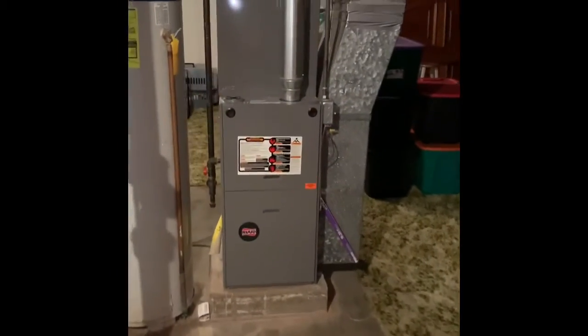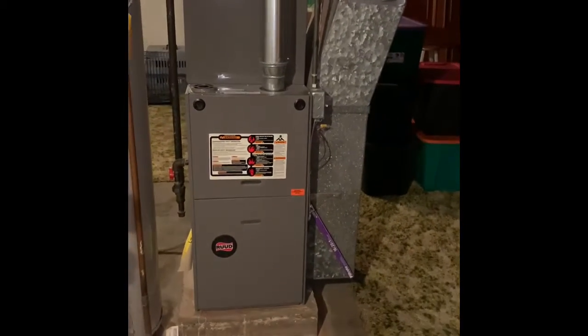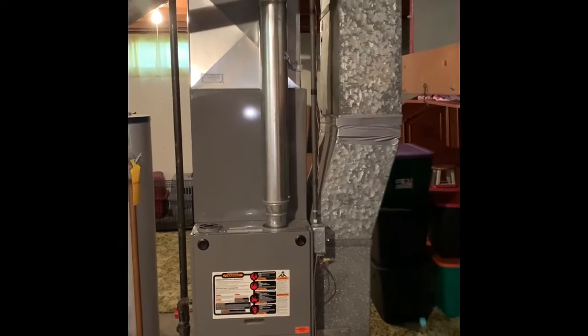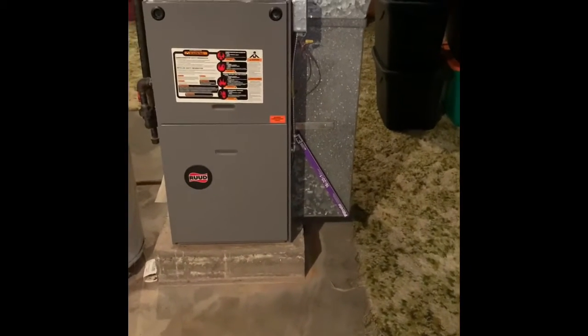Here's our inside portion looking at the AC system only. The system is from 2012 but they've already had two coils replaced, so I'm looking to get rid of this type of system. New coil, new lines will go up and over, face the coil the same way, give options on different types of filters if they want to change anything on that.